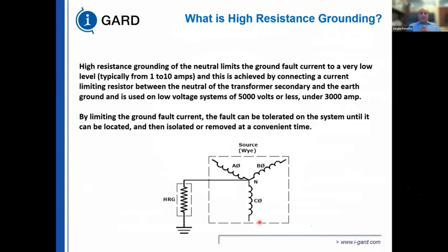High resistance grounding involves replacing that. Typically, when you have a solidly grounded system, all you do is take that neutral point, connect it directly to ground, and you can distribute the neutral. With the high resistance grounded system, you place a resistor. On a 480 volt system, you can put a 27 ohm resistor or a 55 ohm resistor, and you limit the fault current to 10 amps on a 27 ohm resistor or 5 amps on a 55 ohm resistor.